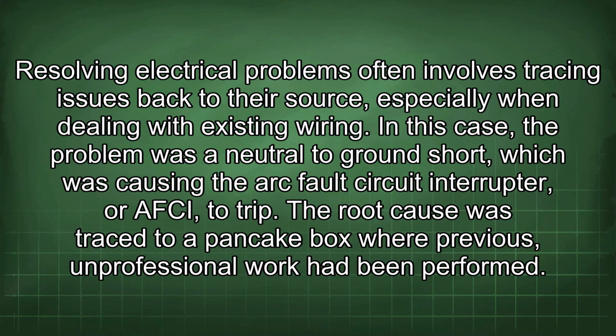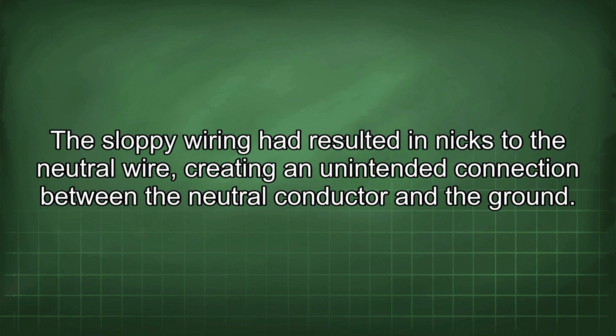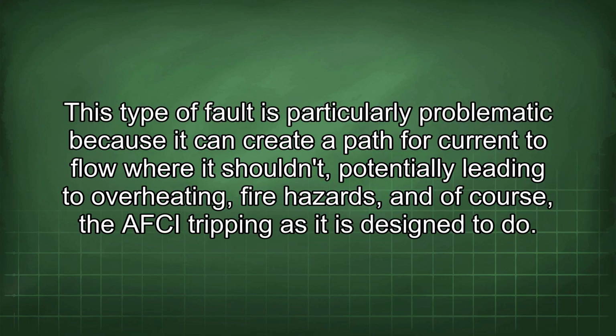Resolving electrical problems often involves tracing issues back to their source, especially when dealing with existing wiring. In this case, the problem was a neutral to ground short, which was causing the arc fault circuit interrupter, or AFCI, to trip. The root cause was traced to a pancake box where previous, unprofessional work had been performed. The sloppy wiring had resulted in nicks to the neutral wire, creating an unintended connection between the neutral conductor and the ground. This type of fault is particularly problematic because it can create a path for current to flow where it shouldn't, potentially leading to overheating, fire hazards, and of course, the AFCI tripping as it is designed to do.